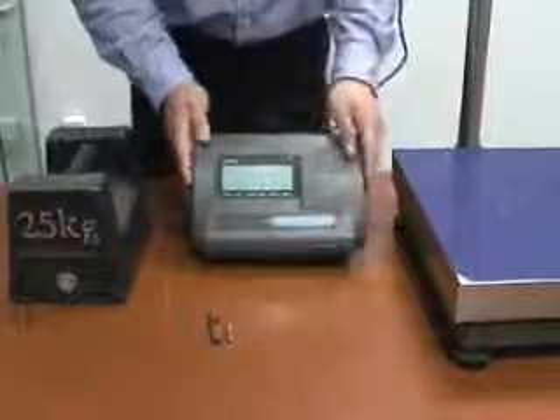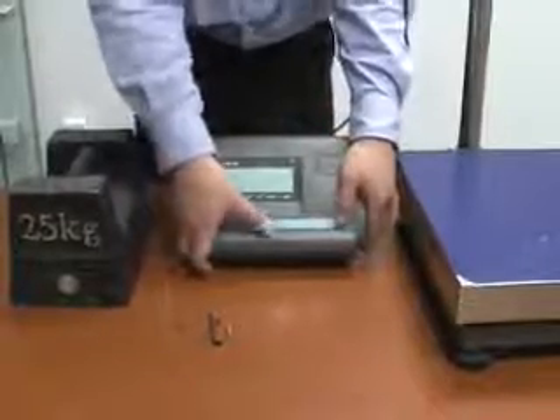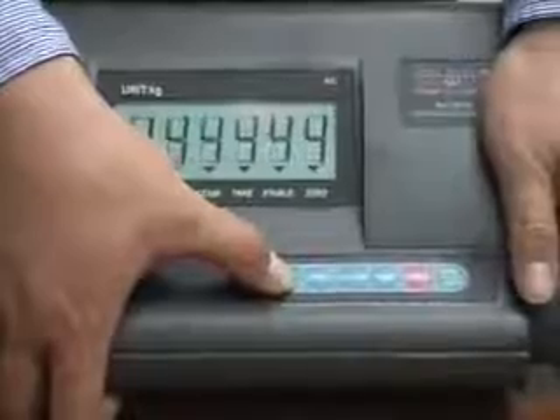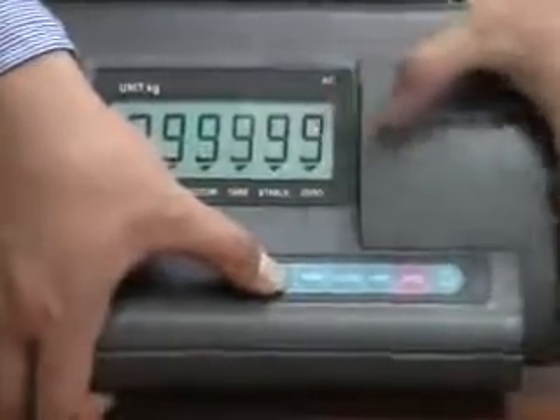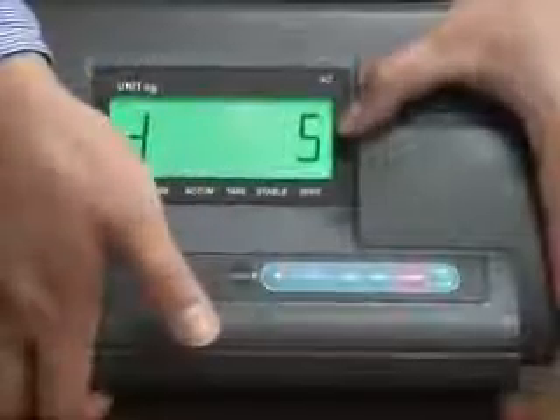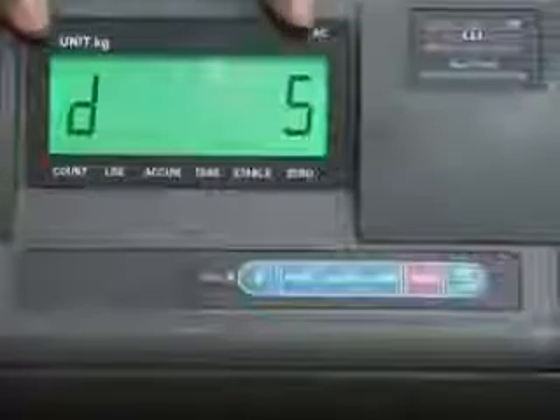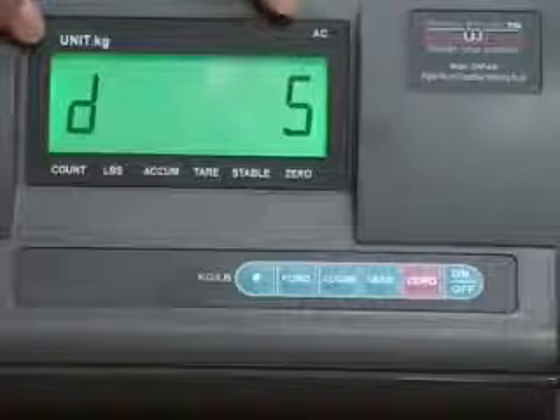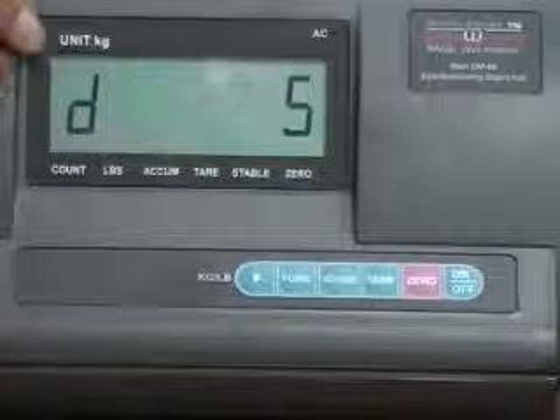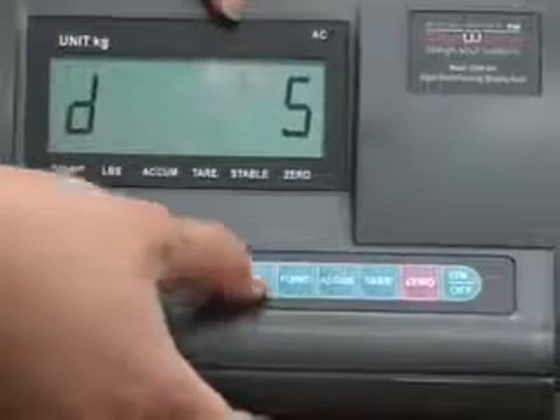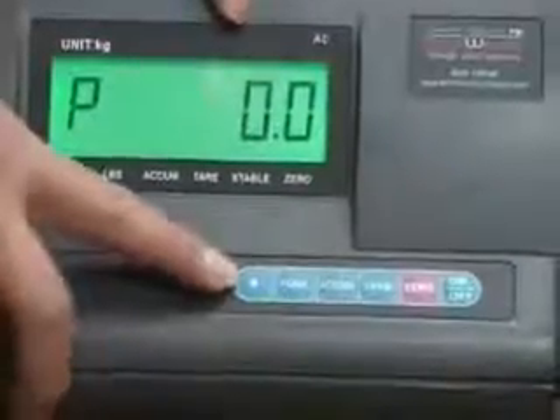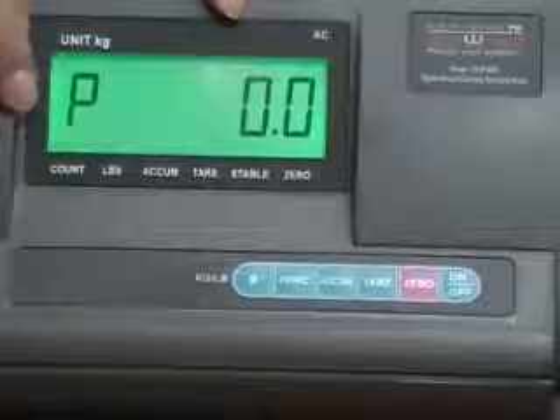First of all, turn off the scale using the soft button. Second step, hold the kg/pound key, hold it, don't release, and turn the scale on. And it will count up until 9. When you see the 9s, you can release the button. It will give you the parameters to choose. D means division. So for this particular scale, let's just choose D5. Press the pound key to confirm and go to the next parameter.